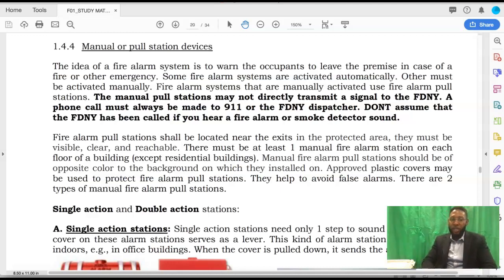So fire alarm pull stations shall be located near the exits of the protected area. They must be visible, clear, and reachable. There must be at least one manual fire alarm pull station on each floor of a building. Manual fire alarm pull stations should be of opposite color to the background on which they're installed. So like that, you see it. It's conspicuous. Approved plastic covers may be used to protect fire alarm pull stations. They help to avoid false alarms.